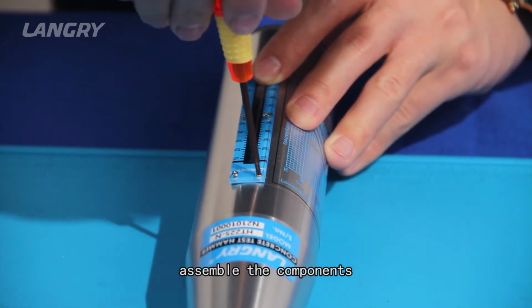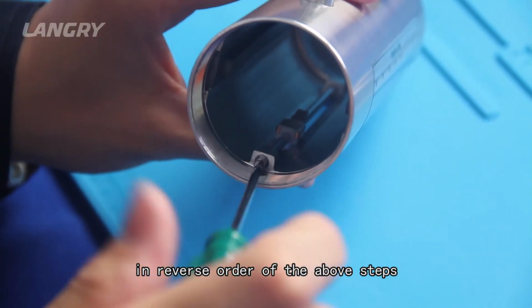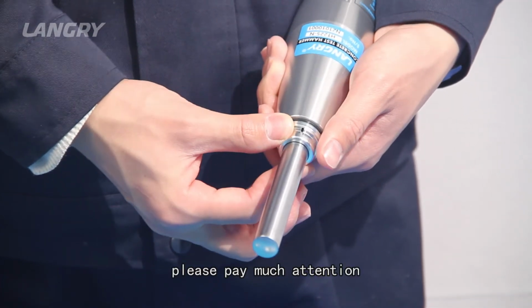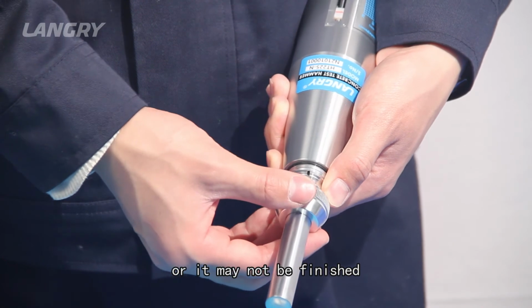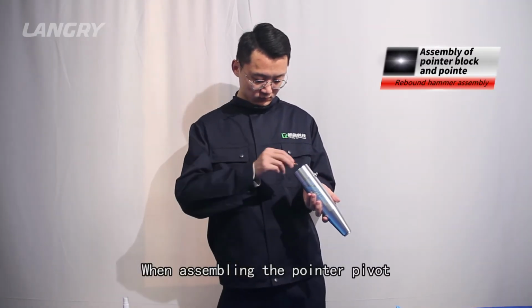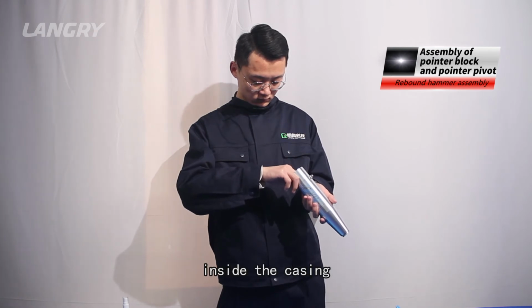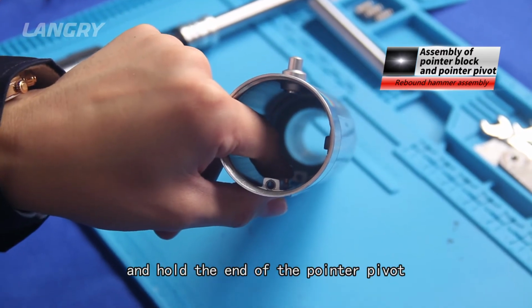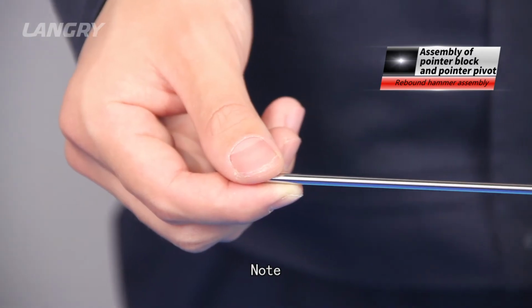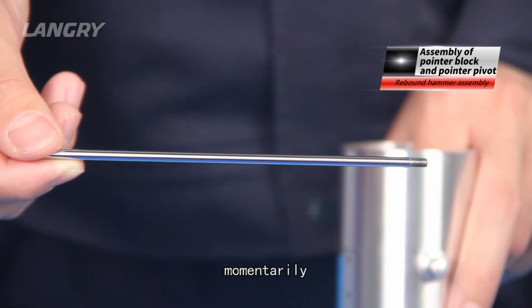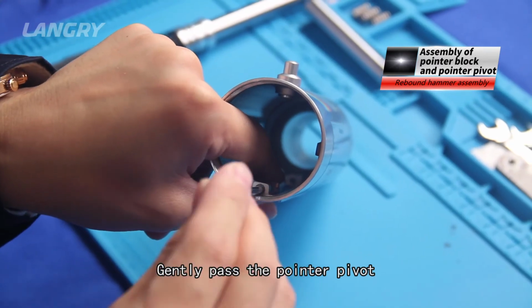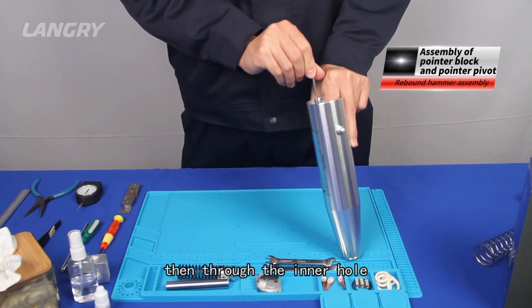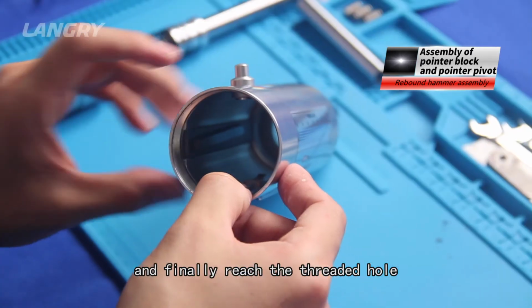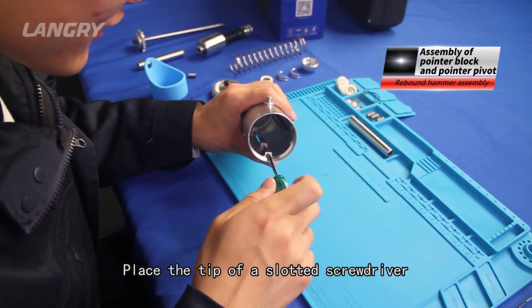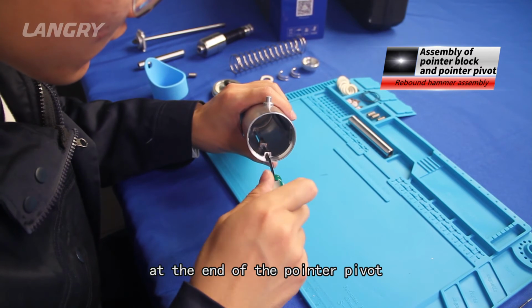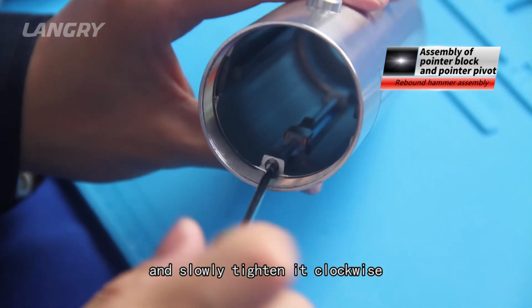After maintenance, assemble the components in reverse order of the above steps. During assembly, please pay much attention to the details or it may not be finished. 1. When assembling the pointer pivot, put the pointer block on the slide inside the casing, press the pointer block with one hand and hold the end of the pointer pivot with the other hand. Note: don't apply oil to the pointer pivot. Gently pass the pointer pivot through the first support hole, then through the inner hole of the pointer block, and finally reach the threaded hole of the second support. Place the tip of a slotted screwdriver in the groove at the end of the pointer pivot and slowly tighten it clockwise.